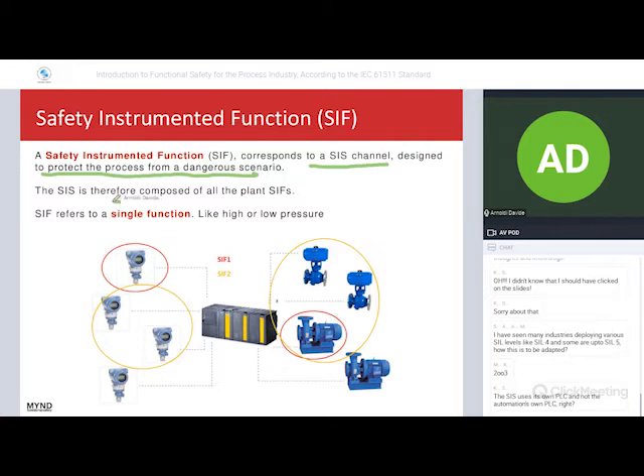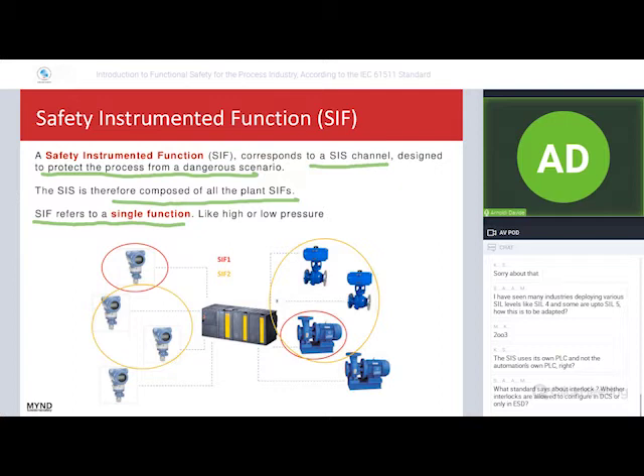The SIS is therefore composed of all the plant SIFs. And the very important thing is that a SIF refers to a single function, like high or low pressure. We can use, for example, one single sensor, one single transmitter for different functions. For example, SIF1, this one in red color, is related to the pressure transmitter, PT.